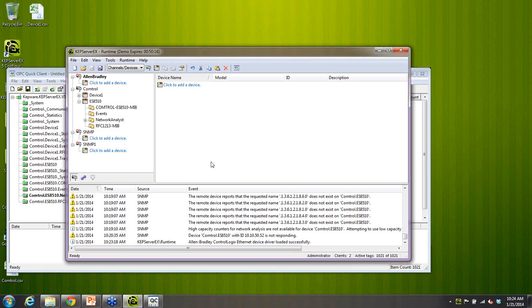So you're really just concerned about getting your data back as fast as possible. Yep, so a great question from Tim. As with connections to PLCs, we would still recommend one channel per device with SNMP. It may depend on your setup. You could have limitations, but one channel per device is our general rule of thumb for most every driver, besides the serial ones. And yes, Joseph, you can send traps.